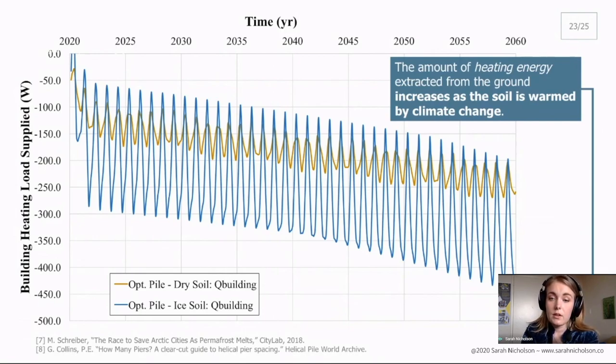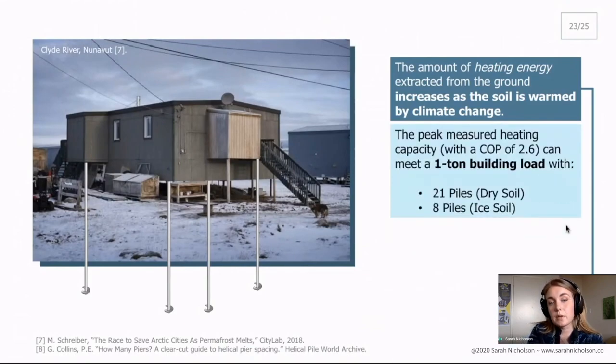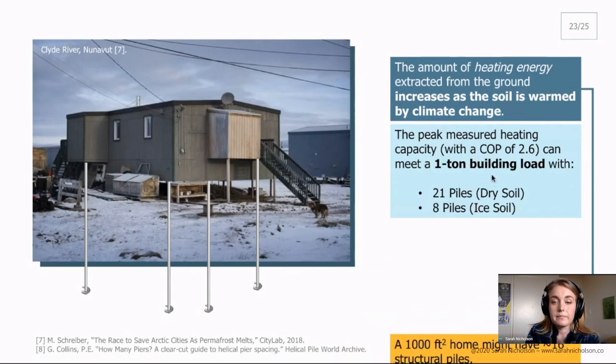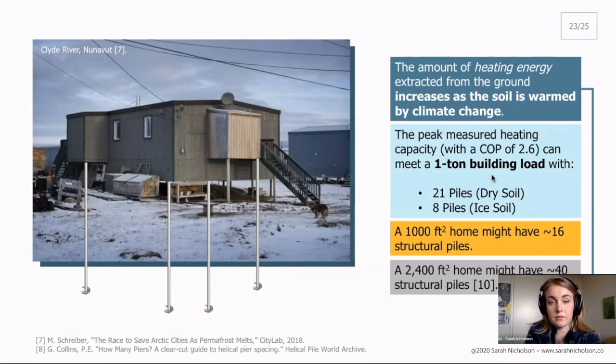Using a peak value from this curve, we can predict the approximate number of piles that might be needed by a building. So assuming that a building requires a 1 ton peak heating load, which is approximately a medium-small size building heating load, it would require 21 piles in dry soil and 8 piles in ice soil to meet that peak load. If we were to take an approximate spacing of 8 feet for these structural piles, a 1,000 square foot home might have 16 structural piles. And a slightly larger home might have 40 structural piles. So these 21 and 8 piles are certainly within reasonable values for this application.